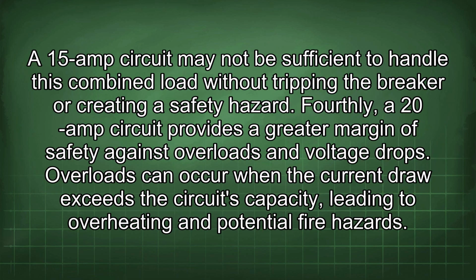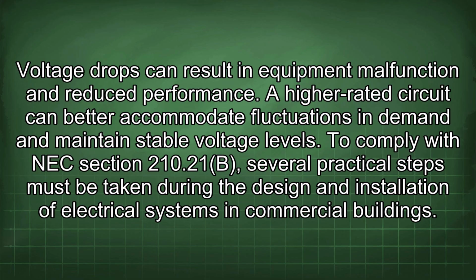A 15 amp circuit may not be sufficient to handle this combined load without tripping the breaker or creating a safety hazard. Fourthly, a 20 amp circuit provides a greater margin of safety against overloads and voltage drops. Overloads can occur when the current draw exceeds the circuit's capacity, leading to overheating and potential fire hazards. Voltage drops can result in equipment malfunction and reduced performance. A higher rated circuit can better accommodate fluctuations in demand and maintain stable voltage levels.